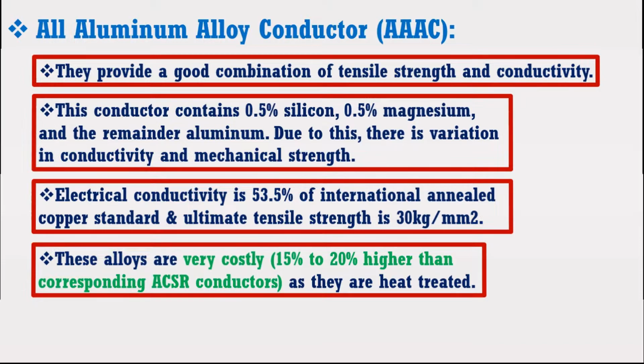It may be noted that these alloys are very costly, almost 15 to 20% higher than corresponding aluminium conductor steel reinforced conductors, as they are heat treated. Now I am going to discuss the advantages of all aluminium alloy conductor. Number 1. Corrosion resistance. All aluminium alloy conductor exhibits excellent corrosion resistance, especially in coastal and polluted industrial areas due to absence of steel core.